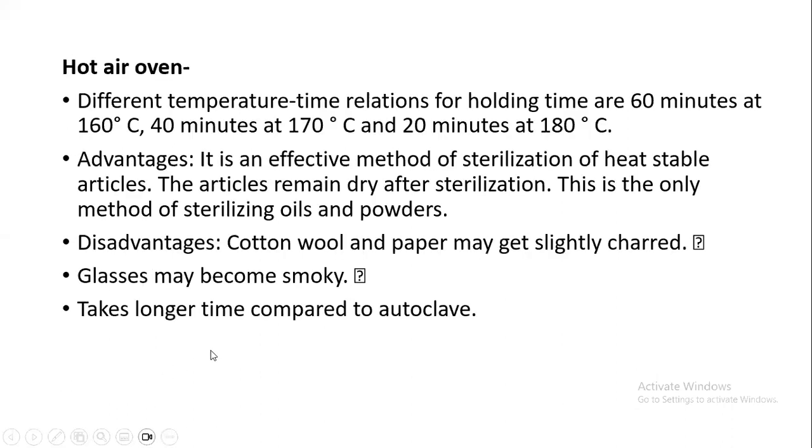Then hot air oven, it is commonly used in the laboratories. So different temperature ranges can be used. Commonly 60 minutes at 160 degrees Celsius is used. If you increase the temperature, then the time required for sterilization will comparatively decrease, as you can see.